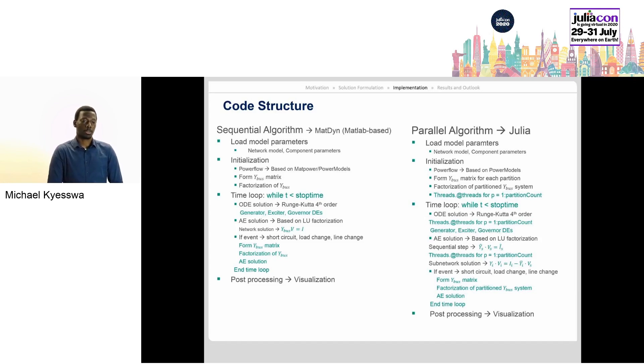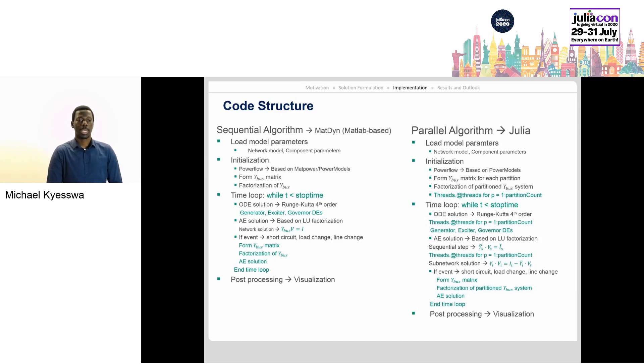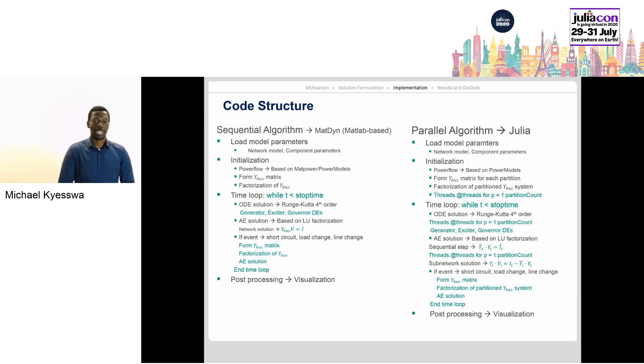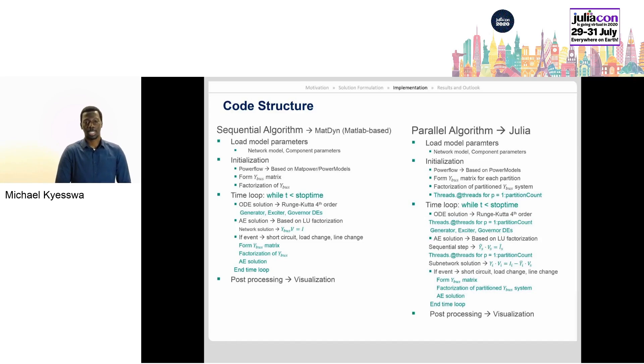The second task is the solution of the algebraic equations of the network. This consists of two steps: the sequential step computing the boundary node voltages, followed by the parallel step for computing the internal node voltages. In case of an event resulting in a change in network topology, the admittance bus matrix has to be reformulated and algebraic equations of the network solved before the next time step. The final post-processing step handles visualization of results using Makie plots.